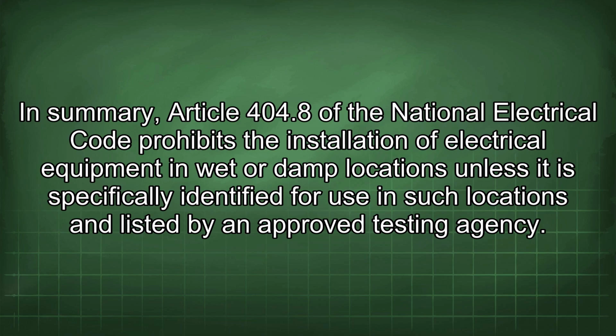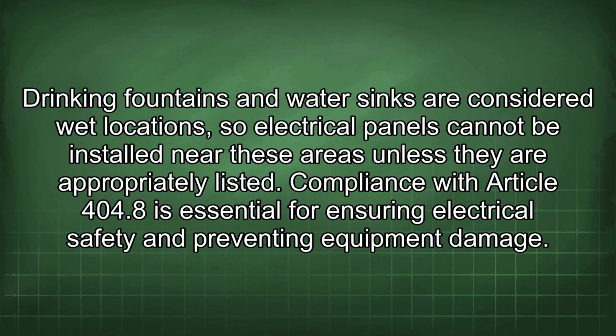In summary, Article 404.8 of the National Electrical Code prohibits the installation of electrical equipment in wet or damp locations unless it is specifically identified for use in such locations and listed by an approved testing agency. Drinking fountains and water sinks are considered wet locations, so electrical panels cannot be installed near these areas unless they are appropriately listed.